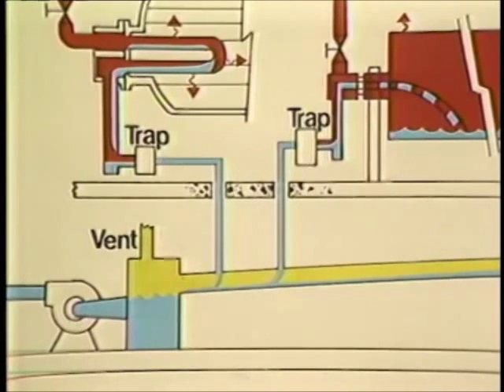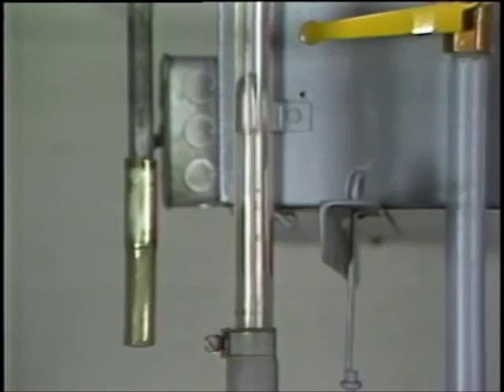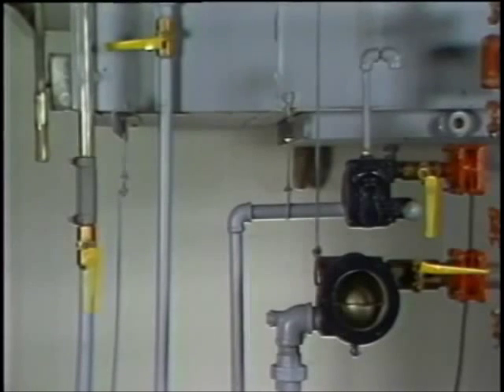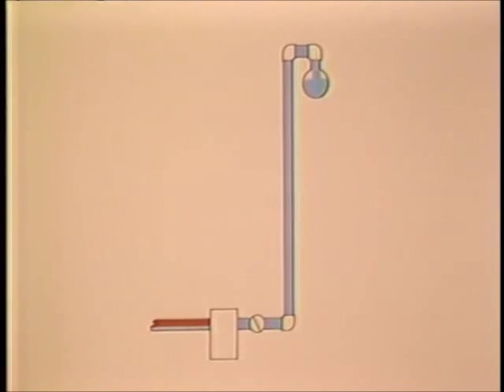Ideally, condensate should flow from the steam trap by gravity to a receiver. Such an arrangement is not always practical, however. In some applications, the only space available for return lines is overhead, so condensate must be elevated from the trap. The force to elevate condensate is provided by the differential pressure across the trap. Since each two feet of lift reduces this differential pressure by one pound, be sure there is adequate pressure both to elevate the condensate and to maintain adequate trap capacity. When elevating condensate, use a check valve either immediately downstream of the trap or integral to the trap, to prevent backflow of condensate into the heat exchanger when the control valve closes.